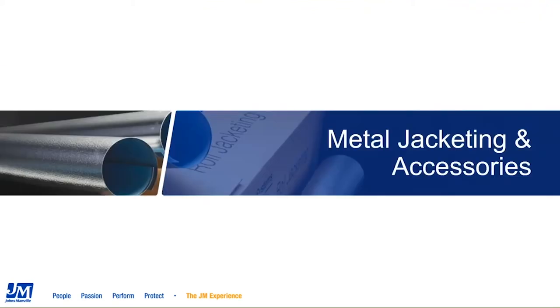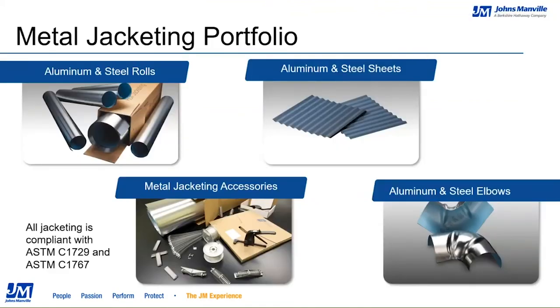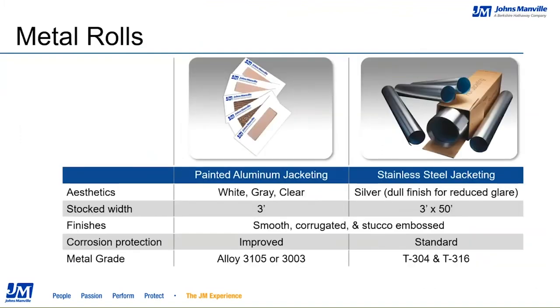All of our jacketing is compliant with ASTM C1729 or C1767 for aluminum and stainless steels. We provide aluminum, painted aluminum, and stainless steel in rolls, sheets, accessories, and elbows. For rolls, painted aluminum is available in clear, white, and gray; stainless steel is typically silver for reduced glare. Finishes available across all metals include smooth, corrugated, stucco embossed, or combinations. Metal grades are 3105 or 3003 alloy for aluminum, and 304 or 316 for stainless steel.